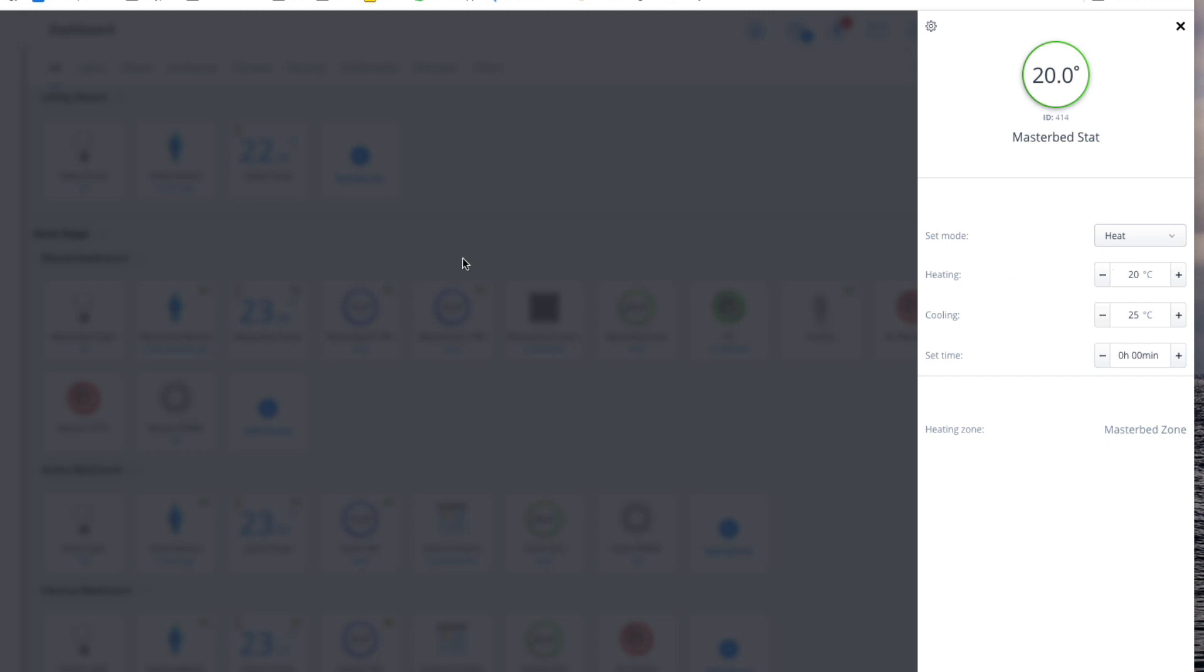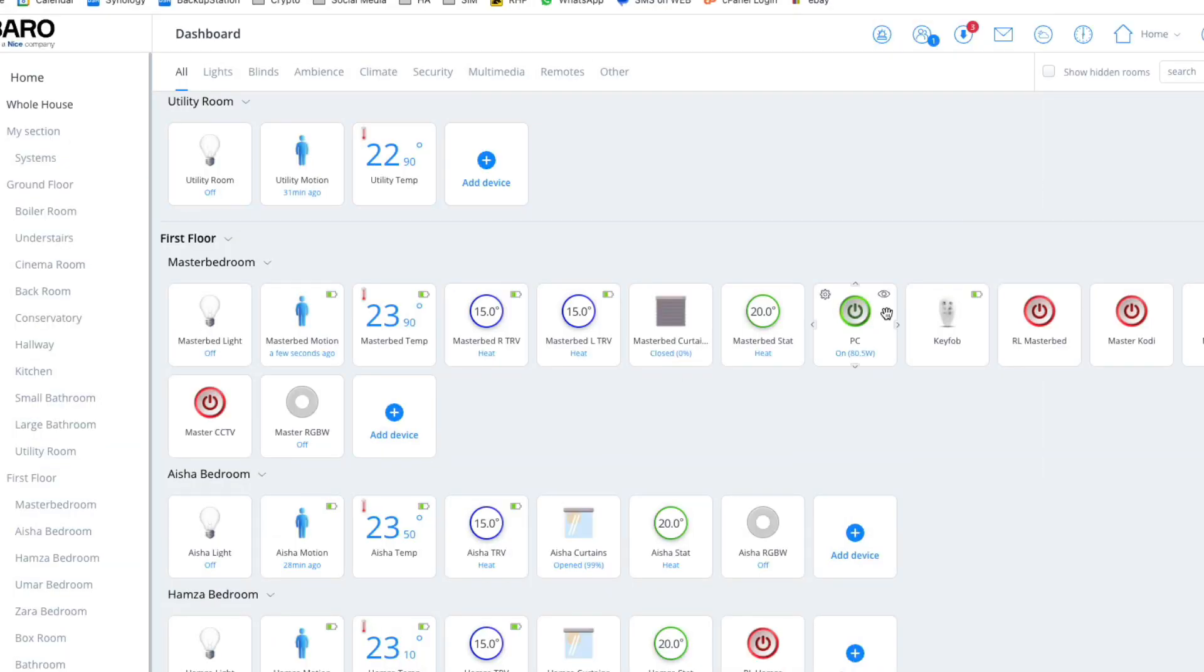So then the climate panel can dictate what's my heating temperature, what's my cooling temperature. And of course, that little QA I've written for heat mode/cooling mode will automatically switch between the two. This is a way to override the thermostats as well. So if I wanted to say have a bit extra heat for three hours, I can just hit set. Conversely, if this was in cooling mode, I could just adjust the cool mode temperature for a certain amount of time and hit set, and it would override it.